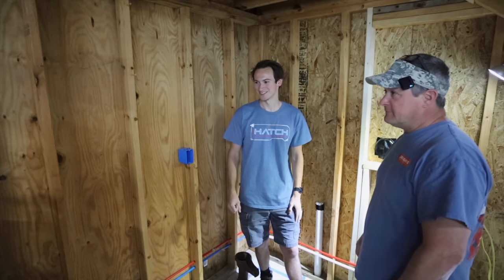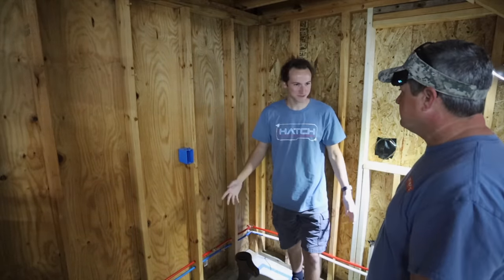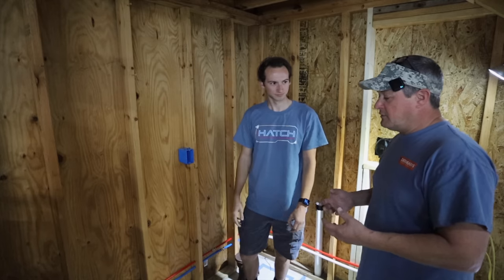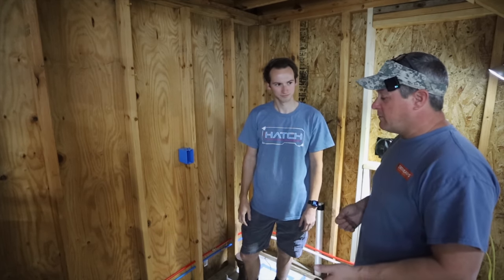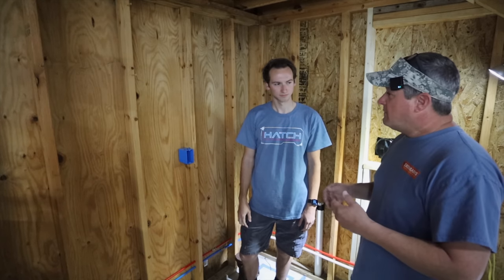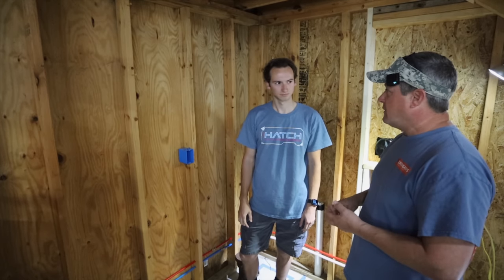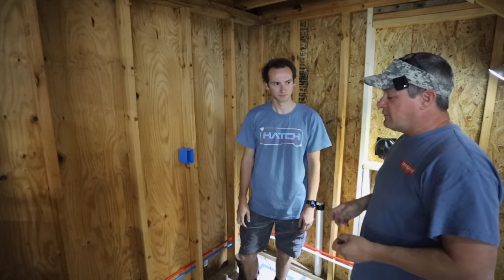So we're in the bathroom now — this is going to be an awesome bathroom. We have a corner shower over here, a sink right here, a window, and we already ran all of our plumbing. We're on the other side of the wall now, thinking about putting our distribution panel here and wondering if we should do it inside or mounted on the outside. Since you've talked about future solar or generators, when we've got power from the electric provider, or on a sunny day running solar, or in an emergency running a generator, it might be a good idea to put the panel on the exterior — surface mount it toward the workroom — so you can come back and make changes later. There will have to be some transfer switches and lockouts to keep everybody safe and prevent back-feeding to the system. Simply by having that box surface mounted, I think it gives you better options.